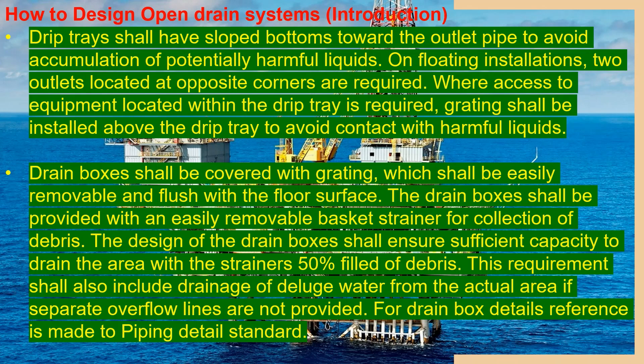Where access to equipment located within the drip tray is required, gratings shall be installed above the drip tray to avoid contact with harmful liquids. Drain boxes shall be covered with gratings which shall be easily removable and flush with the floor surface. The drain boxes shall be provided with an easily removable basket and strainer for collection of debris. The design of drain boxes shall ensure sufficient capacity of drainage with a strainer 50% filled with debris. These requirements shall also include drainage of deluge water from the actual area. If separate overflow lines are not provided, for drain box details reference is made to the piping detail standard.